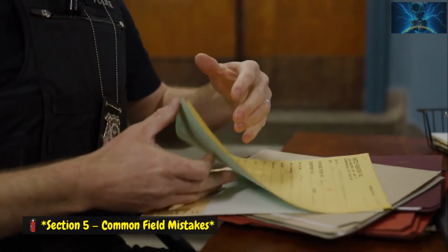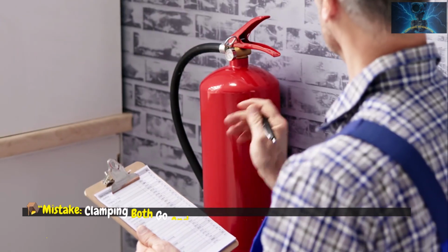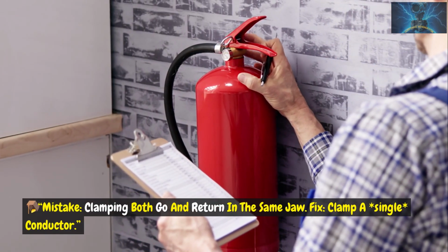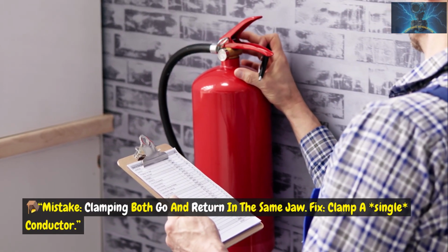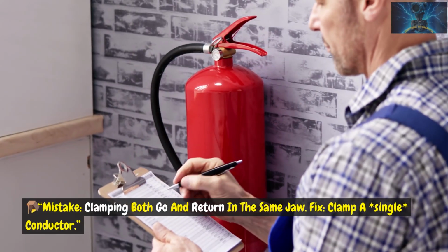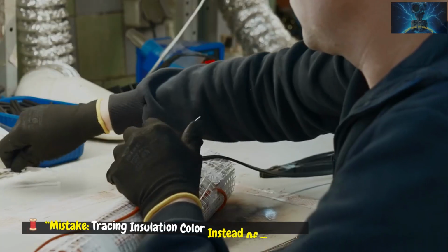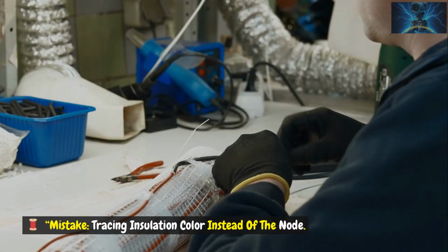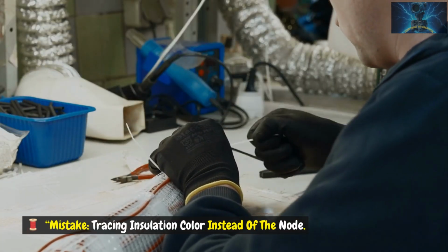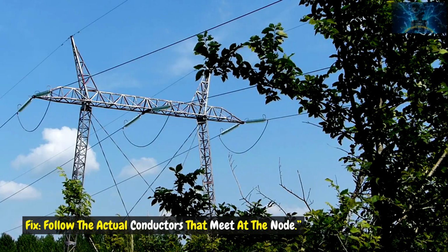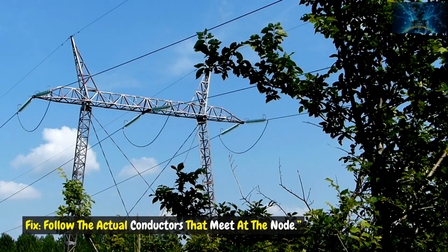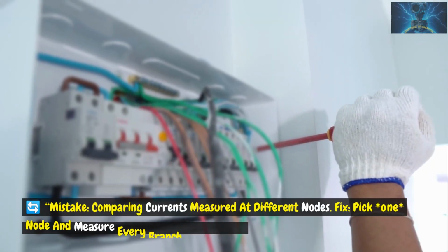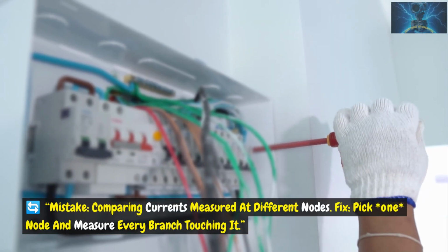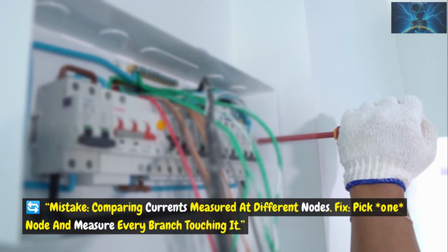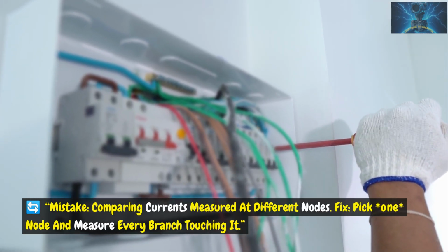Section 5. Common field mistakes. Mistake: clamping both go and return in the same jaw. Fix: clamp a single conductor. Mistake: tracing insulation color instead of the node. Fix: follow the actual conductors that meet at the node. Mistake: comparing currents measured at different nodes. Fix: pick one node and measure every branch touching it.